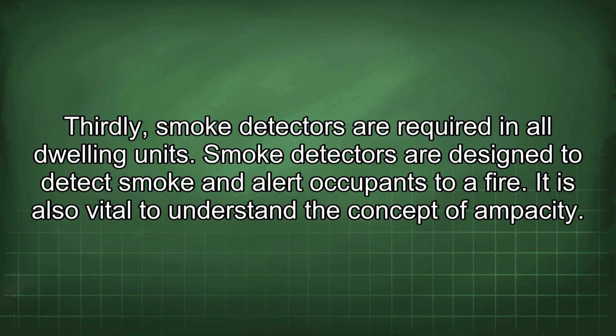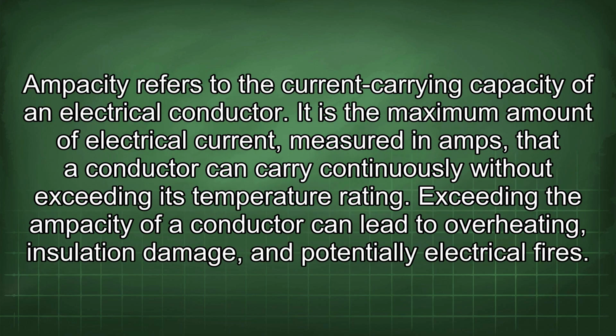It is also vital to understand the concept of ampacity. Ampacity refers to the current carrying capacity of an electrical conductor. It is the maximum amount of electrical current, measured in amps, that a conductor can carry continuously without exceeding its temperature rating. Exceeding the ampacity of a conductor can lead to overheating, insulation damage, and potentially electrical fires.